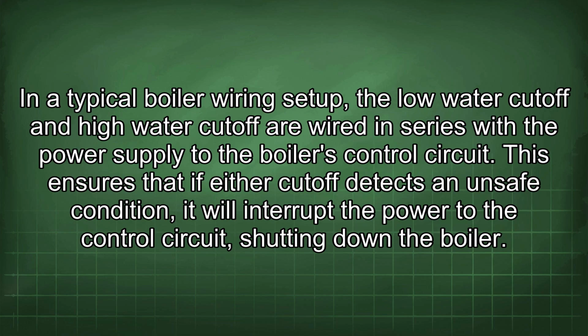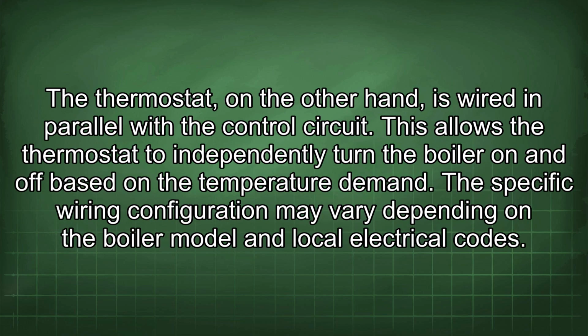In a typical boiler wiring setup, the low water cutoff and high water cutoff are wired in series with the power supply to the boiler's control circuit. This ensures that if either cutoff detects an unsafe condition, it will interrupt the power to the control circuit, shutting down the boiler. The thermostat, on the other hand, is wired in parallel with the control circuit. This allows the thermostat to independently turn the boiler on and off based on the temperature demand.